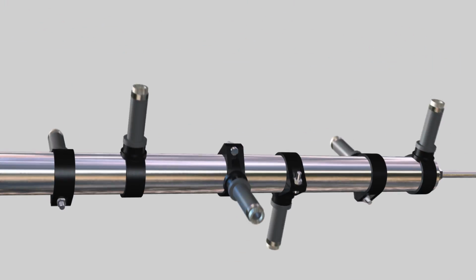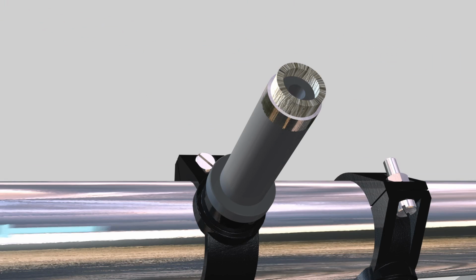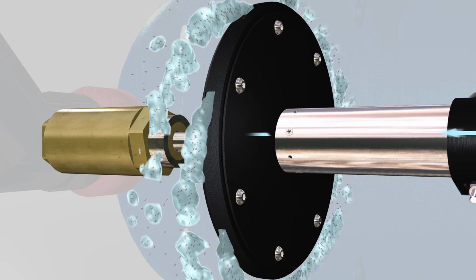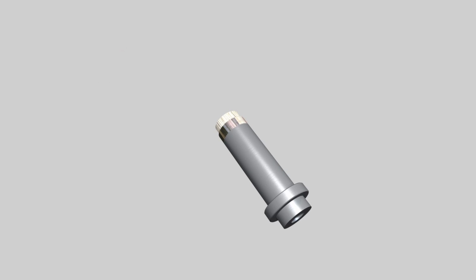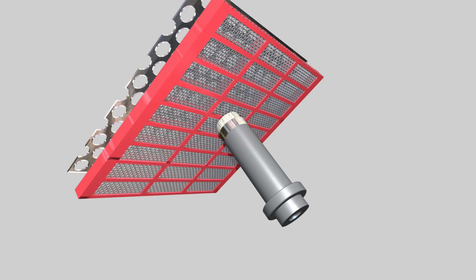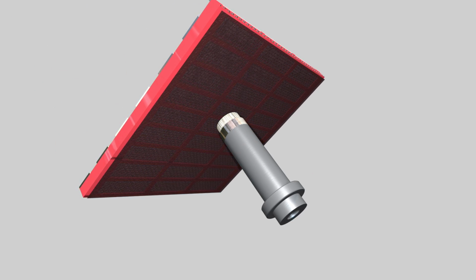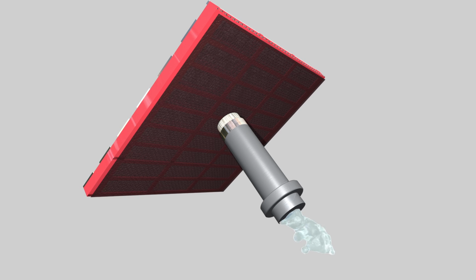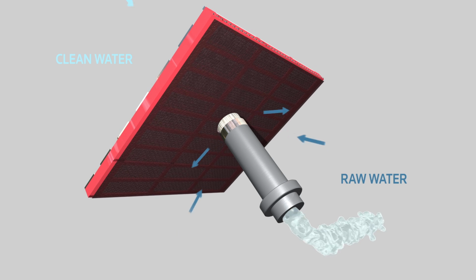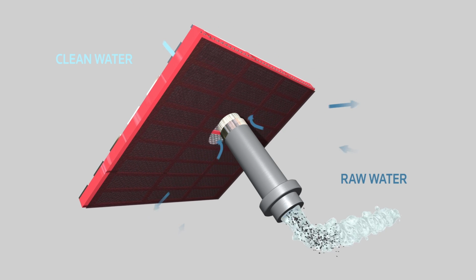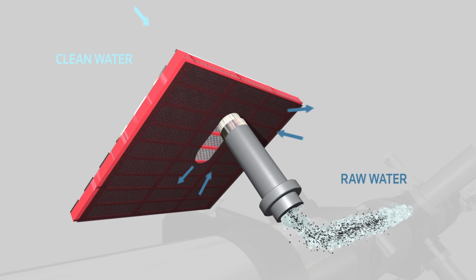The scanner, where the suction nozzles are located with their STF patented nylon bristles, is rotated by the turbine. The drainage valve opening places the nozzle in contact with atmospheric pressure, generating notable suction power through the nozzles, which makes a tiny amount of the filtered water move through the screen in the opposite direction to filtration, dragging the accumulated dirt away and expelling it through the scanner towards the drain.